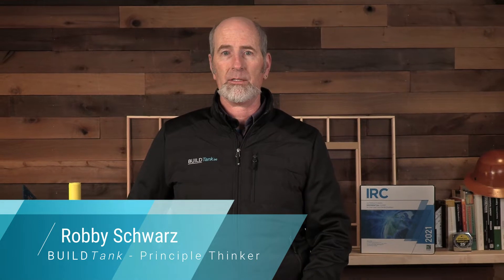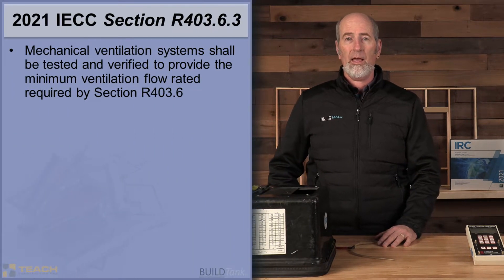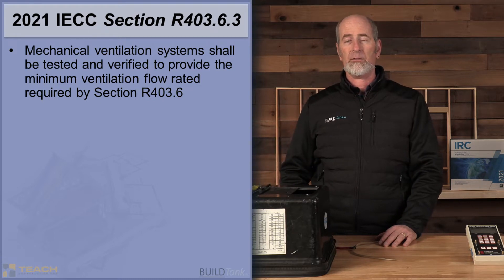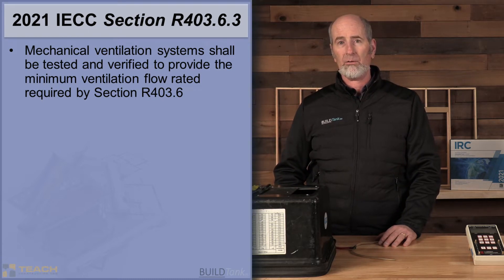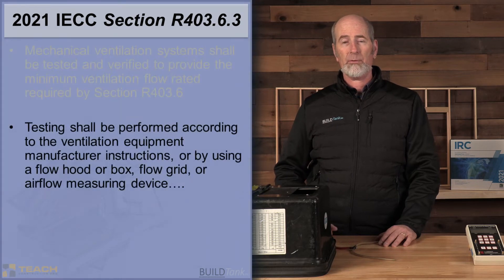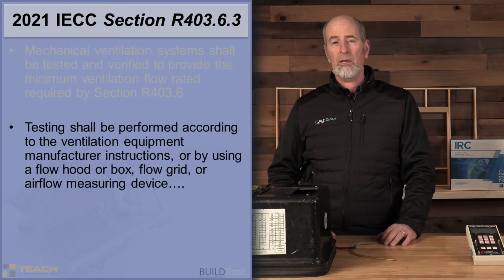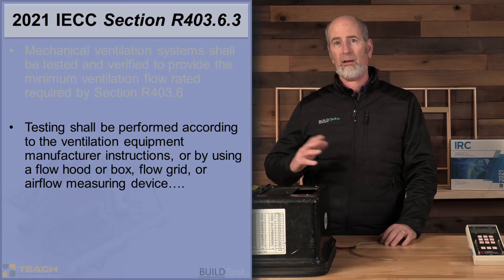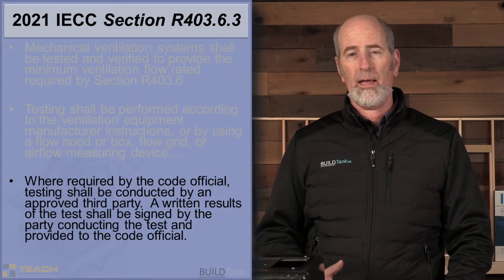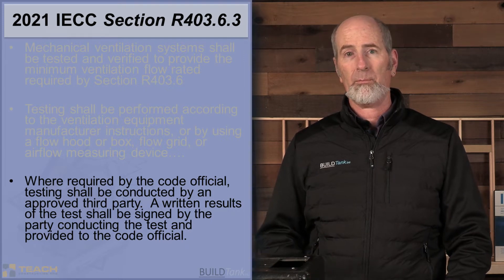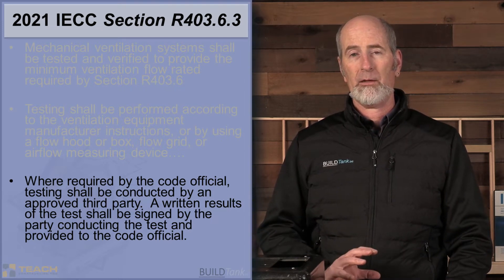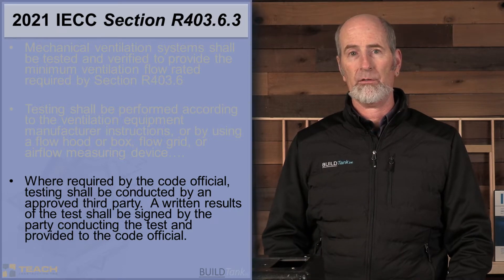Hi, my name is Robbie Schwarz, and we're here today to talk about testing ventilation systems. We need to know about this because the 2021 IECC has a new requirement asking us to verify that ventilation systems in our house — spot ventilation in bathrooms, kitchens, and laundries, and whole house mechanical ventilation — are actually delivering the correct air from inside to outside the house. The code requires this test be performed by an independent third party, who then reports results back to the code official.